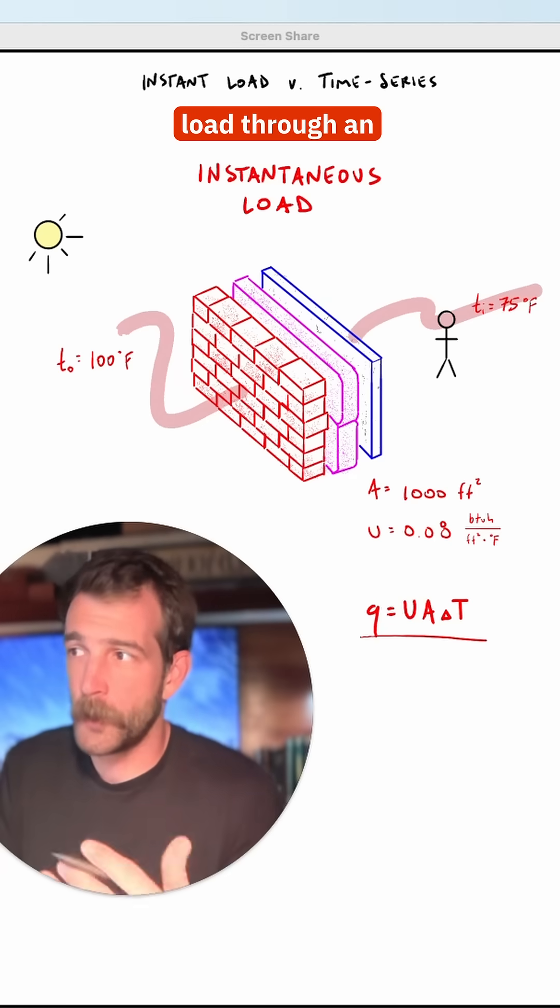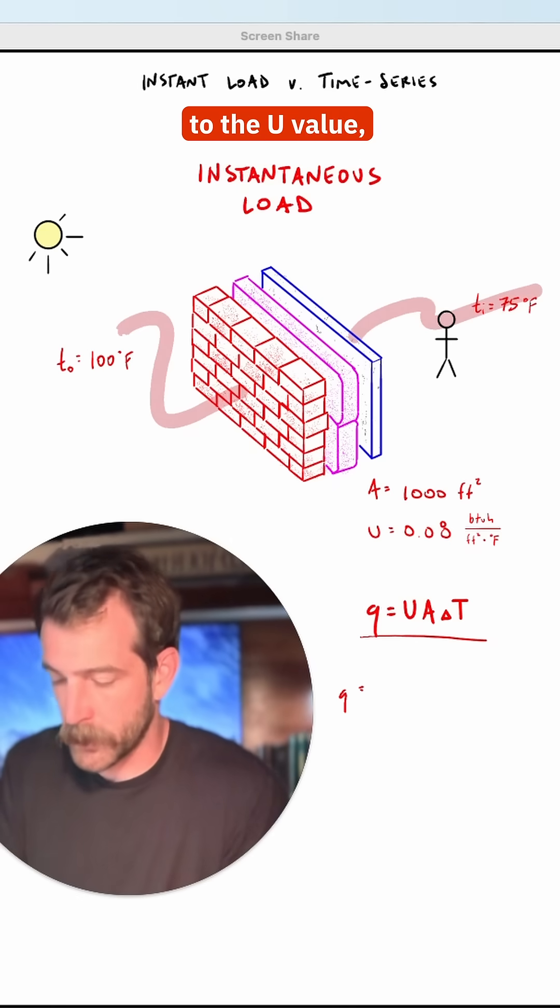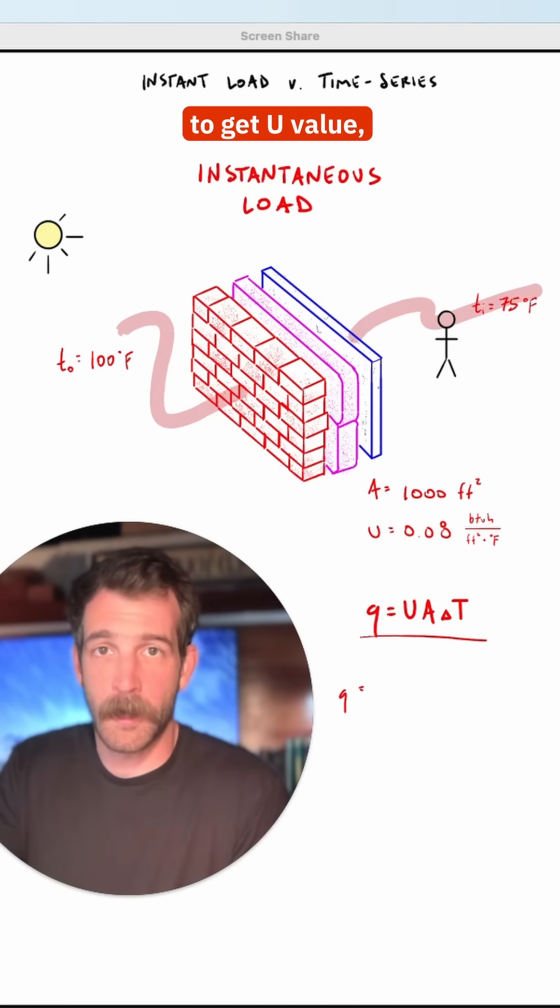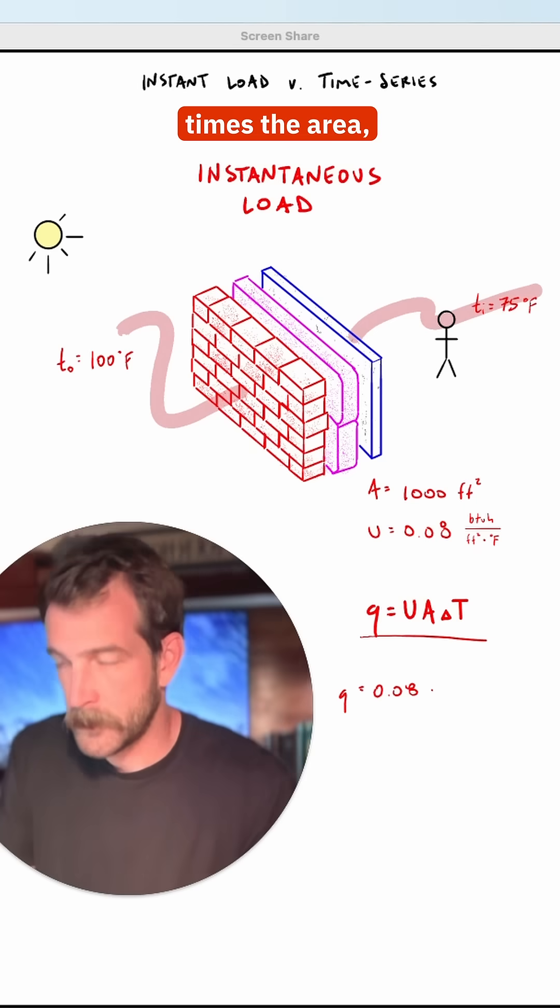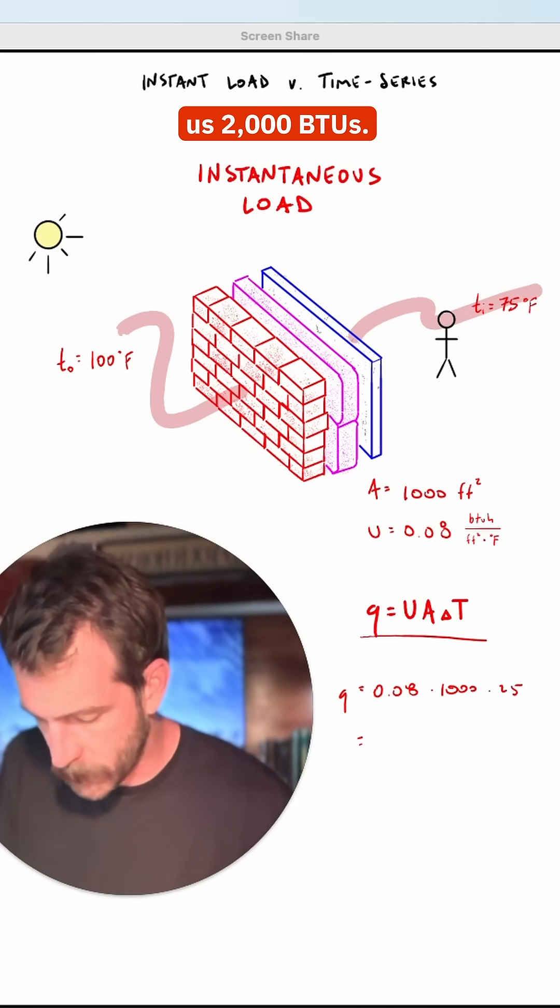This is the basic equation for load through an assembly and is how we'll calculate instantaneous load. So for this wall assembly, it's going to be Q equals the U value, which if you want to know how to get U value, check out the video from yesterday, times the area times delta T. And this will give us 2000 BTUs.